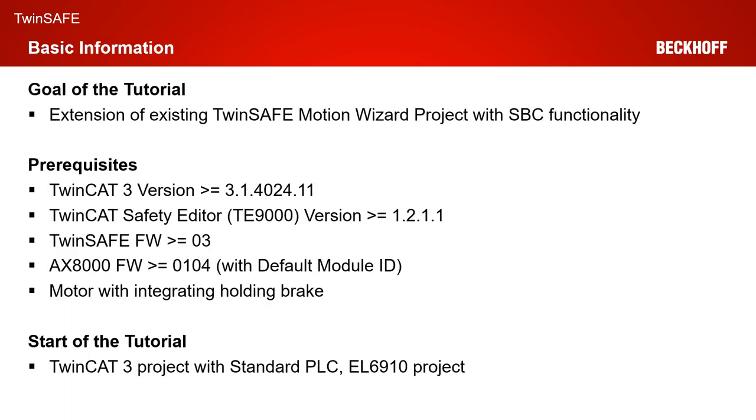The goal of today's tutorial is the extension of an existing TwinSafe Motion Wizard project with SBC functionality. As prerequisites, you need a TwinCAT 3 version greater or equal to 4024.11, a TE9000 version greater or equal to 1211, a TwinSafe firmware on the AX8000 greater or equal to 03.0104 with the default module ID active, and for today's tutorial you need a motor with integrated holding brake.